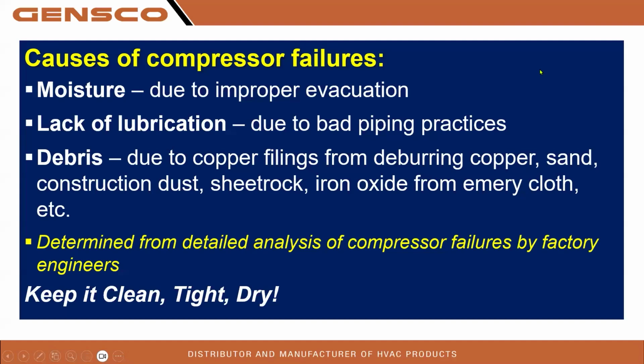The major causes of compressor failure are, of course, moisture due to improper evacuation, causing acid and wearing down the insulation. A lack of lubrication could be due to bad piping practices, or your homeowner has not changed his filter in 2 years.